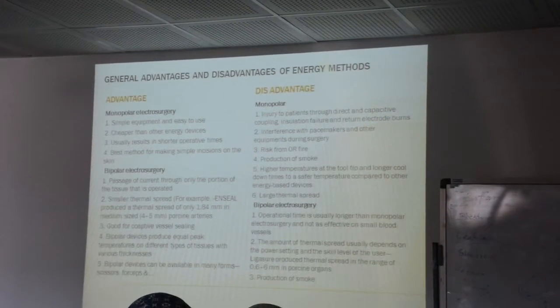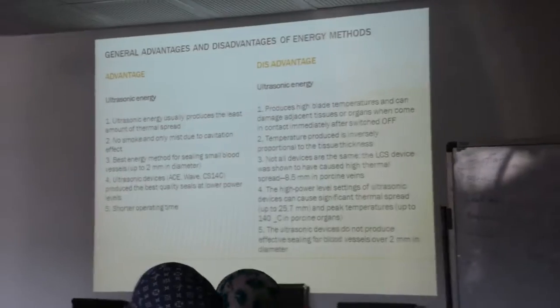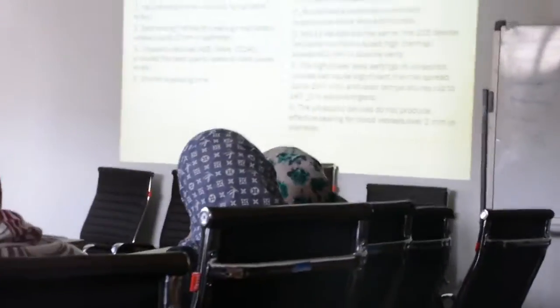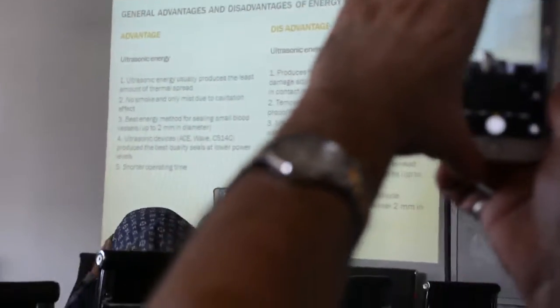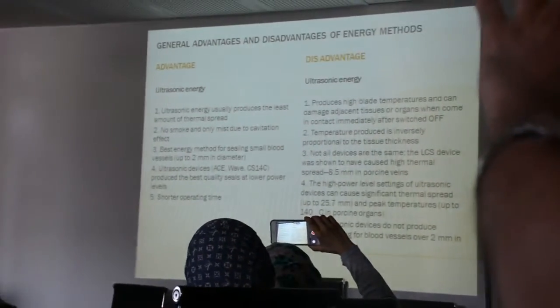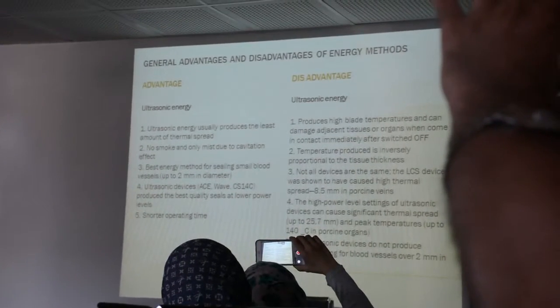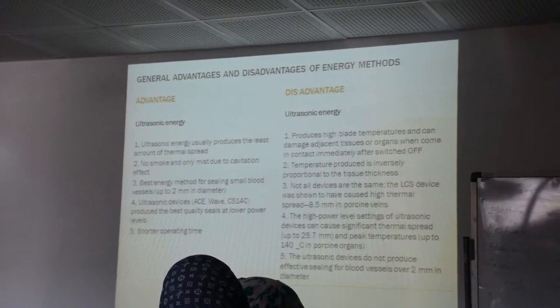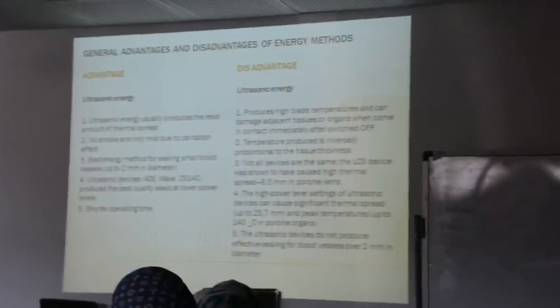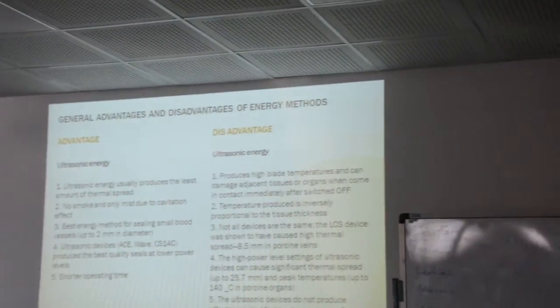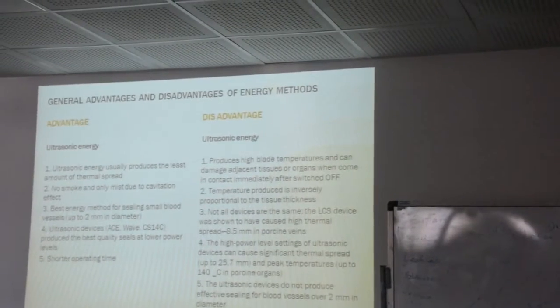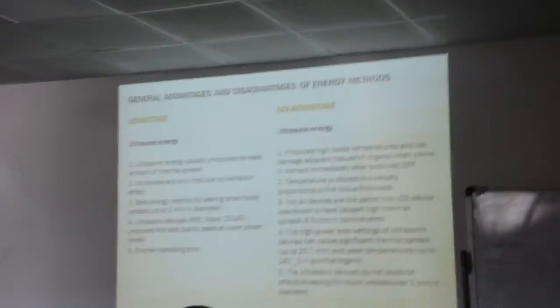Production of smoke. Advantage of ultrasonic energy: it usually produces the least amount of thermal spread, no smoke and only mist due to the cavitation effect. It is the best energy method for sealing small blood vessels up to 2 millimeters in diameter. The ultrasonic device ACE Wave CS14C produces the best quality seals at lower power levels, with shorter operation time.